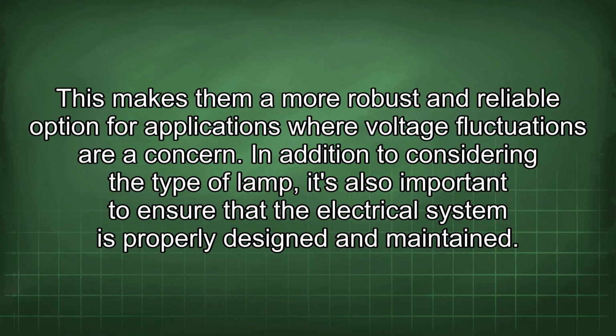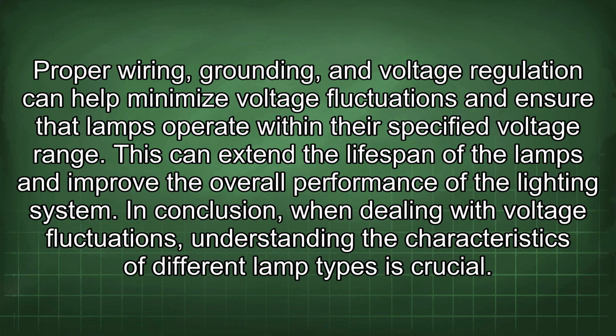concern. In addition to considering the type of lamp, it's also important to ensure that the electrical system is properly designed and maintained. Proper wiring, grounding, and voltage regulation can help minimize voltage fluctuations and ensure that lamps operate within their specified voltage range. This can extend the lifespan of the lamps and improve the overall performance of the lighting system.